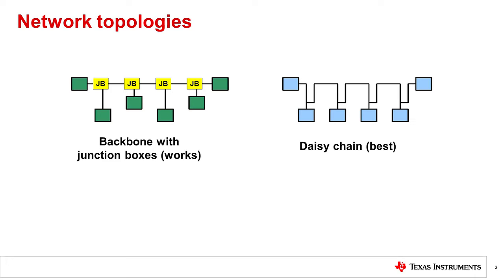The RS-485 standard suggests that nodes be networked in a daisy chain. In this topology, the participating drivers, receivers, and transceivers connect to a main cable trunk via short network stubs. The interface bus can be designed for full duplex or half duplex transmission. An alternative to the daisy chain topology is the junction box approach, which should be implemented in a way to minimize stub lengths and thus reduce reflections.